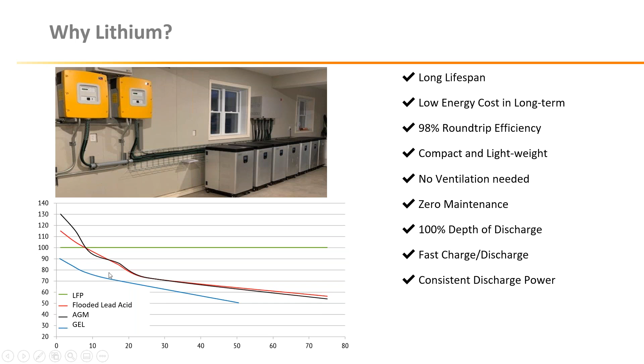But if you have a flooded lead acid, an AGM, or a gel battery, you can see that as your current goes up — say you're pushing current to a specific load in the house — your capacity is going to drop. For example, if you have a 50 amp load and you're pushing 50 amps through a lead acid battery that's fully charged, you're actually getting less power at that 50 amps, meaning you won't have the actual capacity that the nameplate of that lead acid battery claims. So keep that in mind — LFP is straight across the board, while lead acids drop in capacity as current goes up.